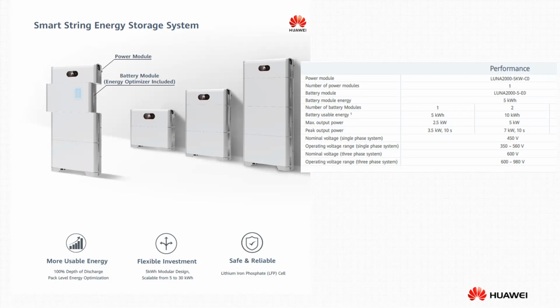If it exceeds that, then it will trip, since the rated power drawn from the battery should be 2.5. If you have two battery modules, then you double up all the specs. So your storage will be 10 kilowatt hour, 5 kilowatt discharge at a given time, and then a surge power of up to 7 kilowatt for 10 seconds.